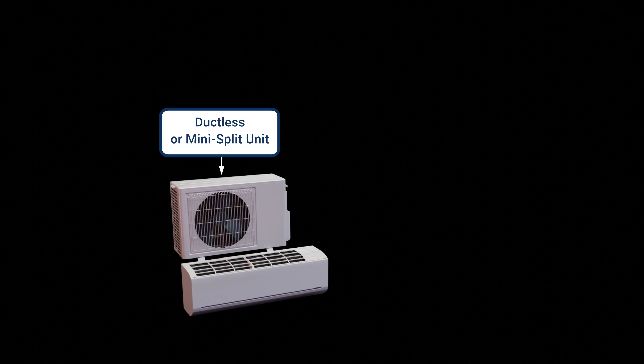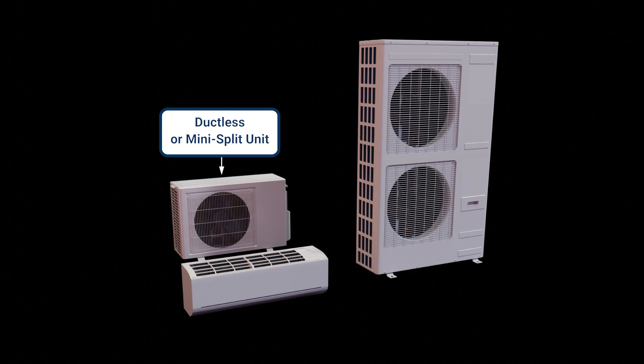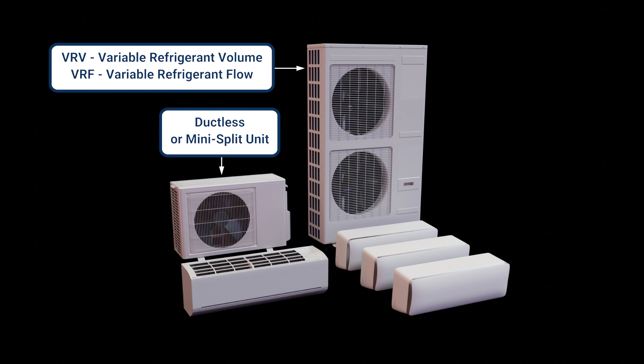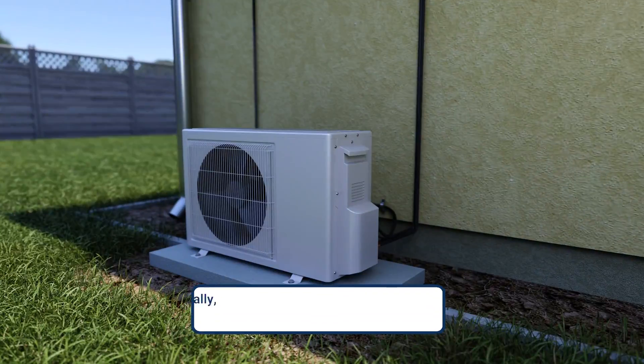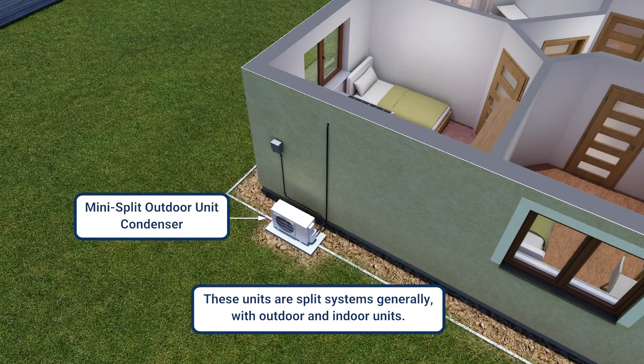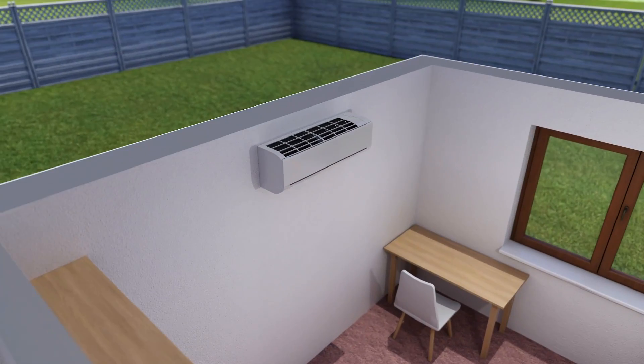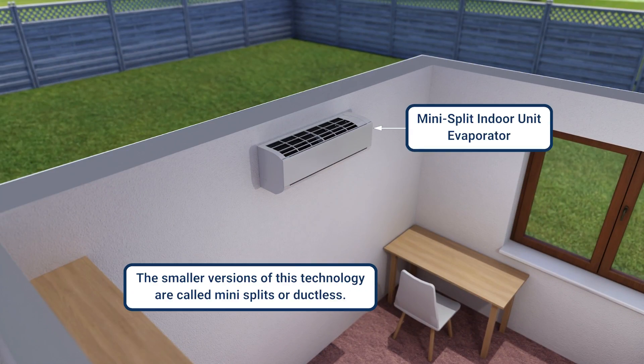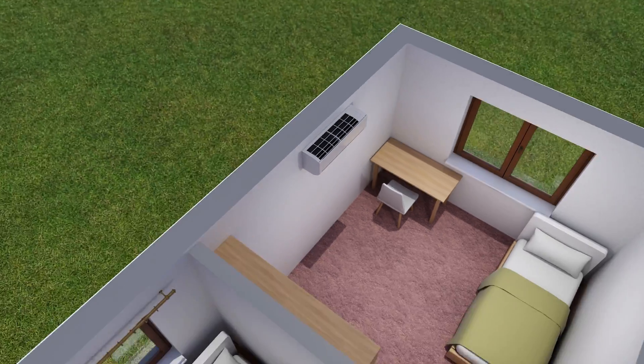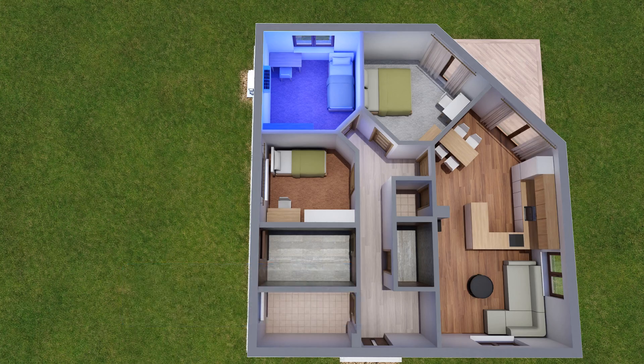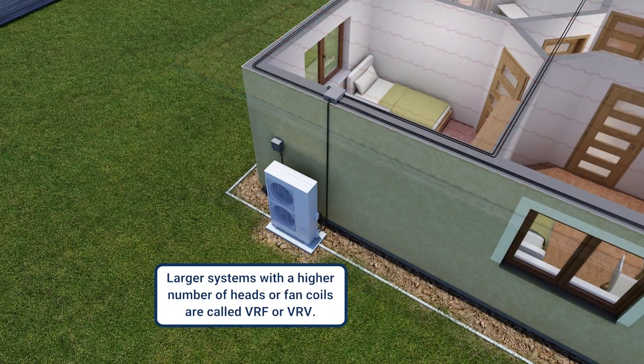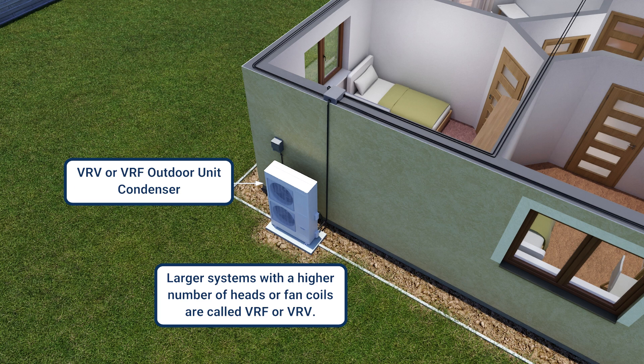Ductless or mini-split units, along with variable refrigerant flow and variable refrigerant volume systems in commercial, offer precise temperature control to multiple zones or rooms, often without ductwork or with less ductwork. These units are split systems generally, with outdoor and indoor units. The smaller residential versions are usually called mini-splits or ductless, and the larger systems with a higher number of heads or fan coils are called VRF, Variable Refrigerant Flow, or VRV, Variable Refrigerant Volume.